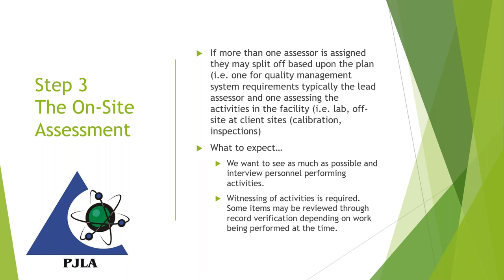Witnessing of activities is required for our on-site assessment. It's sometimes impossible to witness a complete test from start to finish, but we want to witness at least a portion of that test — that's part of our accreditation criteria. If there's nothing available to show us, we at least expect you to make the best effort to show us a portion of a test, even if it's a sample you've developed. There are times we'll do record verification if no work is available to witness.